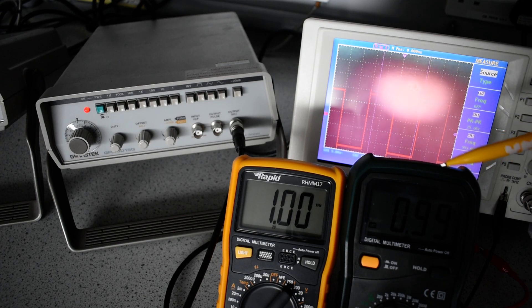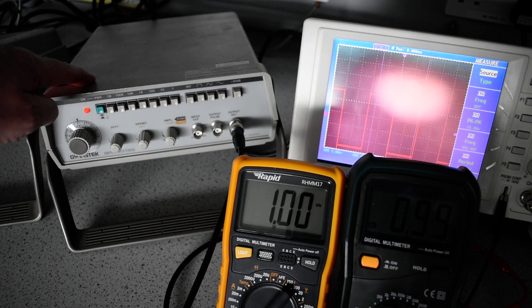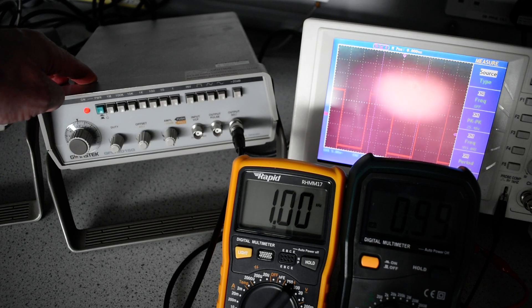But given the fact that we've got three different test instruments measuring very similar values, that would give us a high confidence level that what we are measuring is accurate. So this box is calibrated within manufacturer specification.